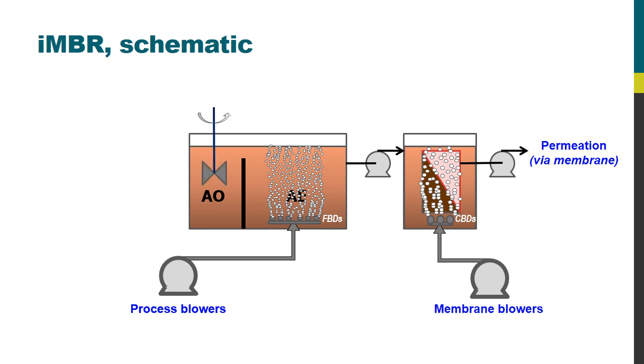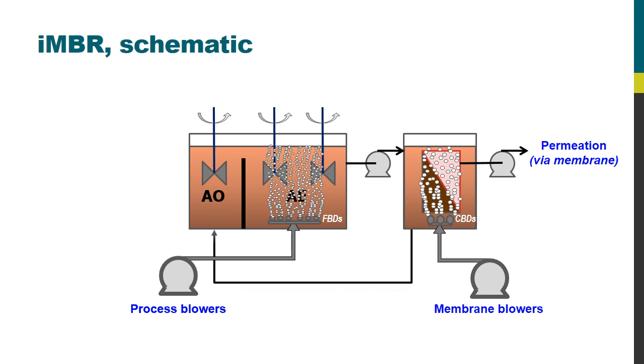These tanks are normally large enough to require some kind of mechanical agitation, and the sludge from the membrane tank is normally returned to the anoxic zone. That process tank is then fed with sewage. There's normally some kind of fine screen required in order to protect the membrane, and that screen is going to be somewhere between one and two millimeters normally.